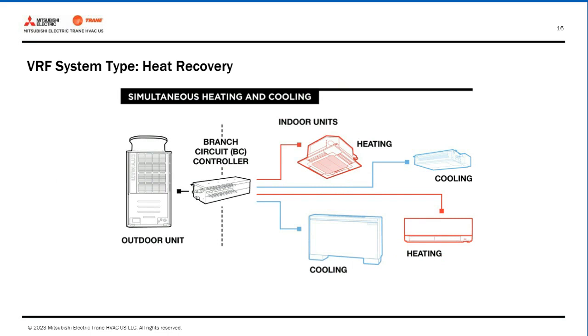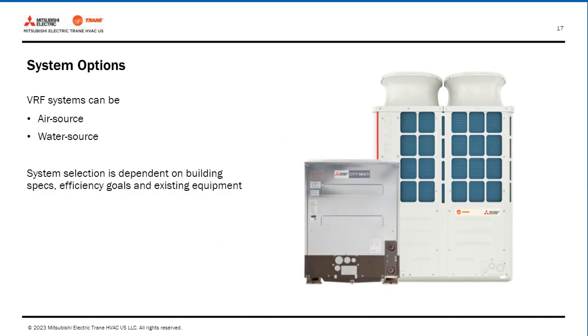And alternately, we can also provide simultaneous heating and cooling in multiple zones by cycling the refrigerant between an outdoor unit and indoor units, which is called heat recovery. The system can be flexible to zones that are occupied versus those not in use, and the heat recovery systems are what's specified for most mixed-use buildings, including the credit union building that we've been talking about. Depending on the location of your building, your efficiency goals, or existing equipment, there's two options. You've got air-cooled or a water-cooled or water source system, which is what we've got at Credit Human.